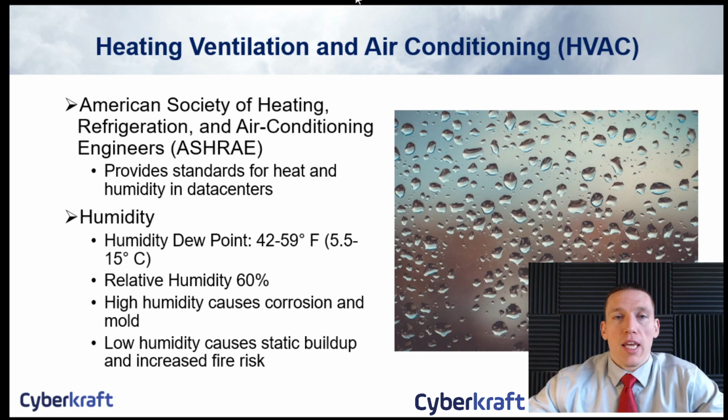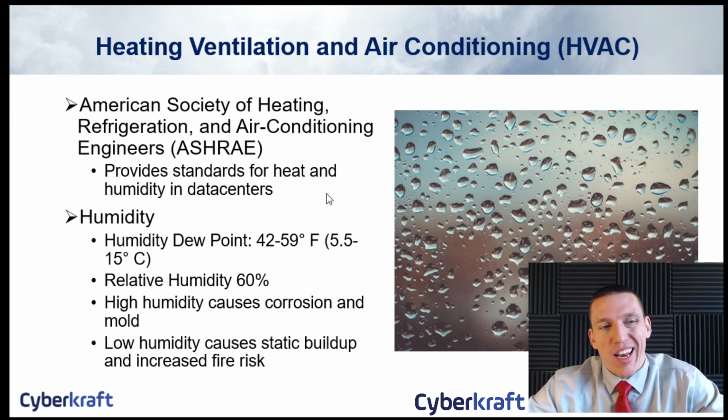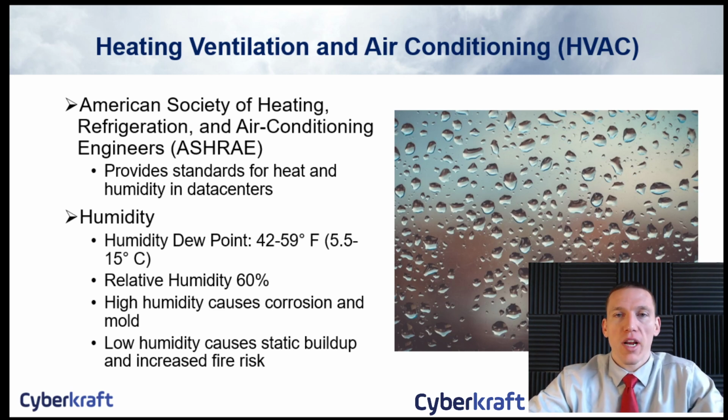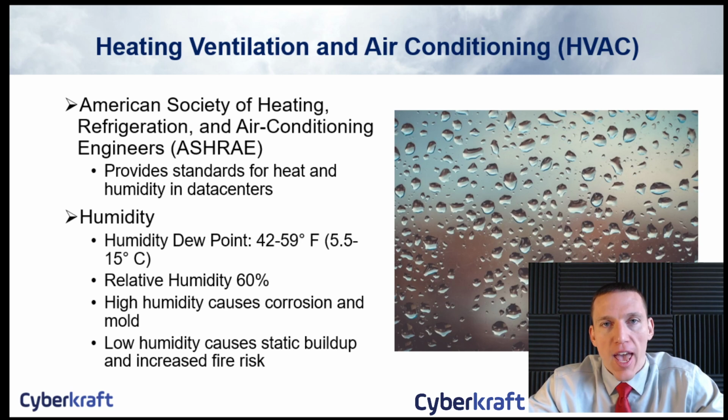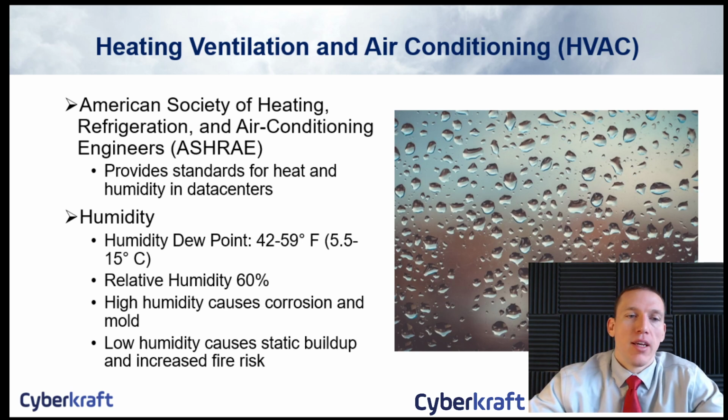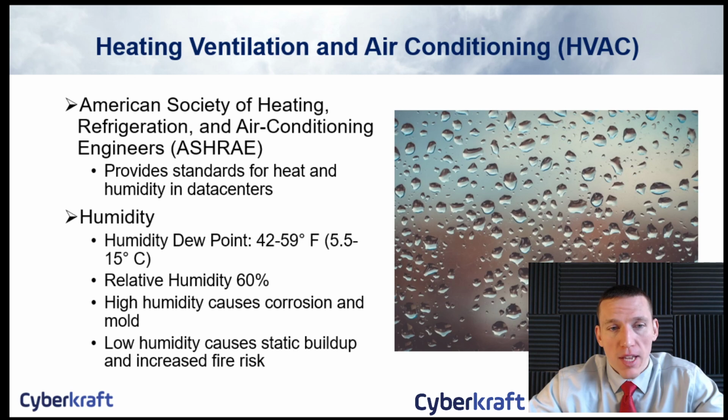Okay, so when it comes to heating and temperature, the authority is the American Society of Heating, Refrigeration, and Air Conditioning Engineers, or ASHRAE. Okay? They provide standards for heating and humidity when it comes to data centers and electrical components. When it comes to humidity, ASHRAE recommends a dew point between 42 and 59 degrees Fahrenheit, or 5.5 to 15 degrees Celsius. Relative humidity is 60%.